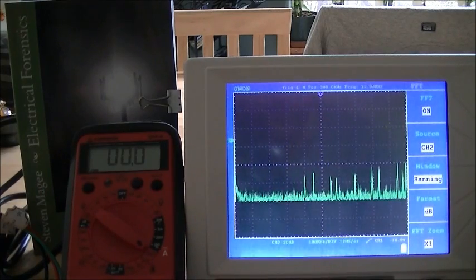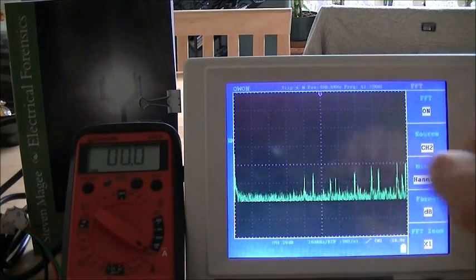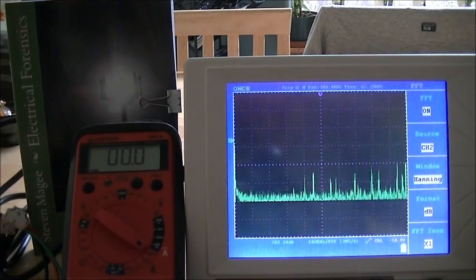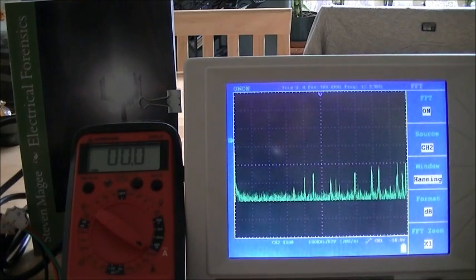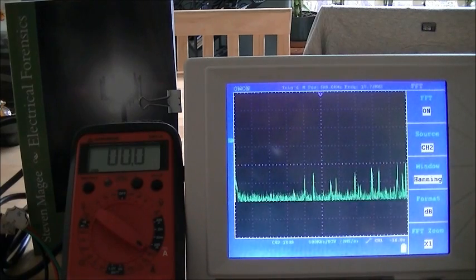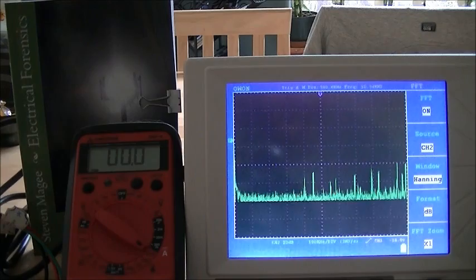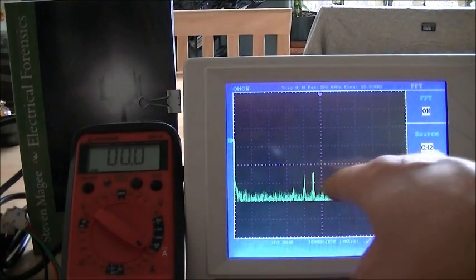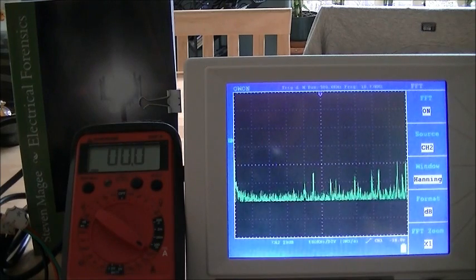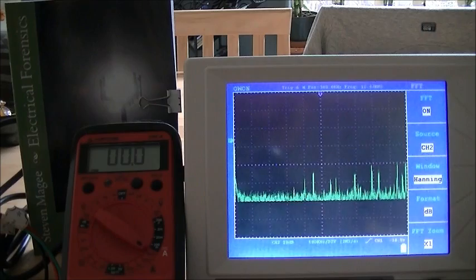This is 100 kilohertz per division and you'll notice that we get all these spikes. This all appears to be the AM radio band over on the right, so they appear to be radio stations that are on the grounding system. If you were to hook your radio into the grounding system you may actually get good radio reception. You can see there's a general background noise on the waveform. What we're going to do now is water the ground rods, get them really wet and see what happens.